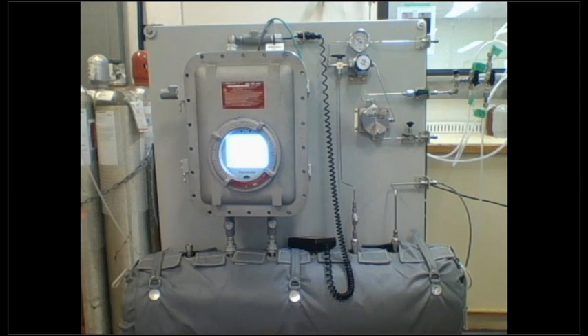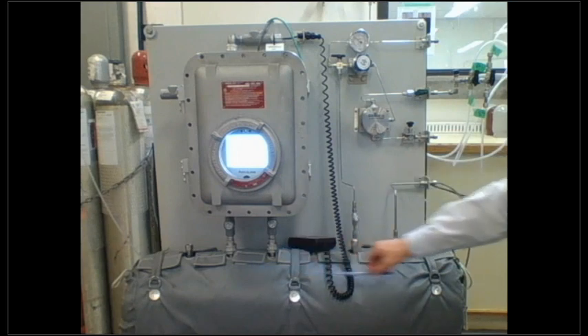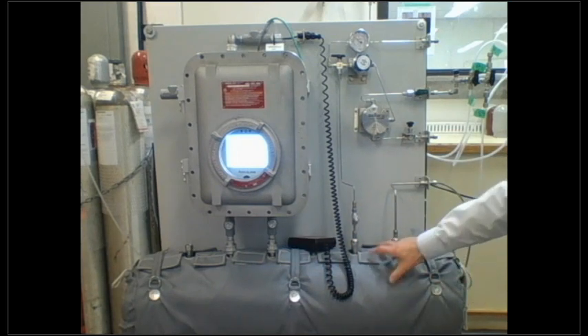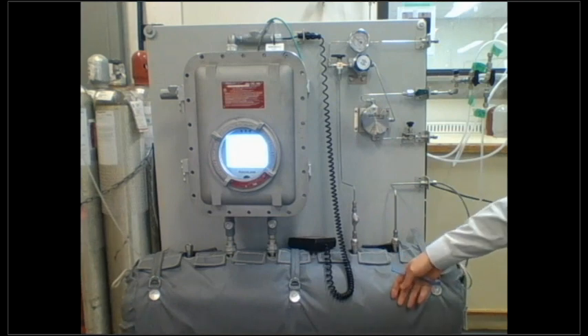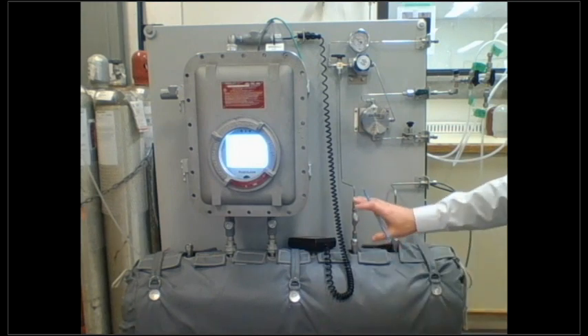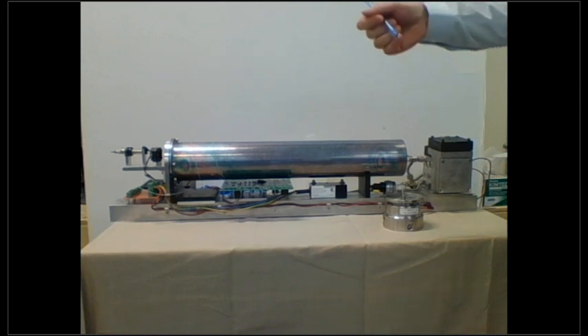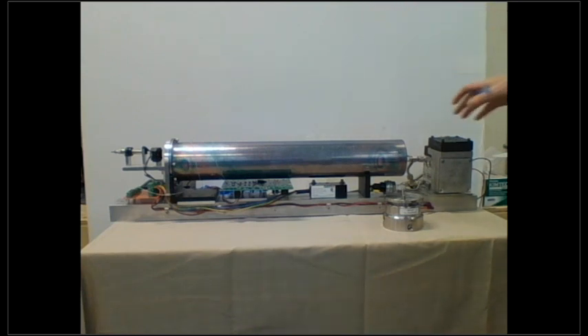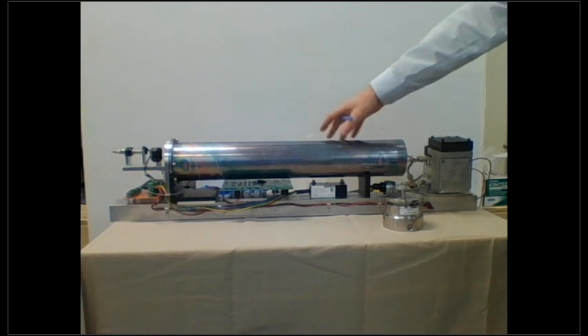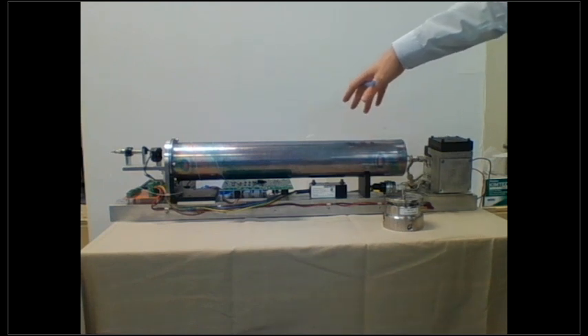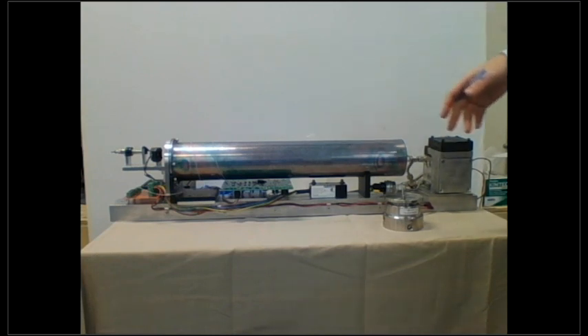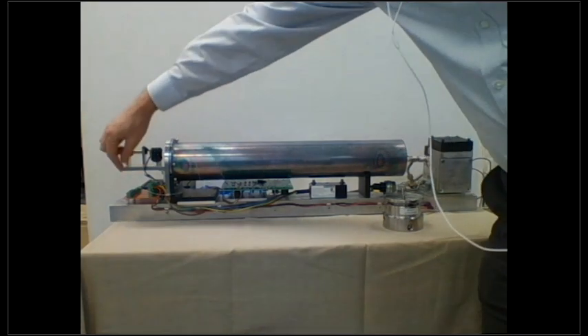So again, the bottom enclosure is temperature controlled. It's got this insulated blanket on it just to help keep the temperature controlled to 40 degrees Celsius. But to actually see what's inside this lower enclosure, I'm just going to swing my camera around a little bit. The components that are inside the lower explosion-proof housing are on a rail. This entire rail is accessible. The end caps of that explosion-proof housing screw off, and there's basically 2 bolts that hold the rail in place. You undo a couple of the gas fittings. The electrical can be undone by just simply pulling the terminal blocks out of this little connector here. And the whole thing comes loose. You can pull it out, put it on the bench.